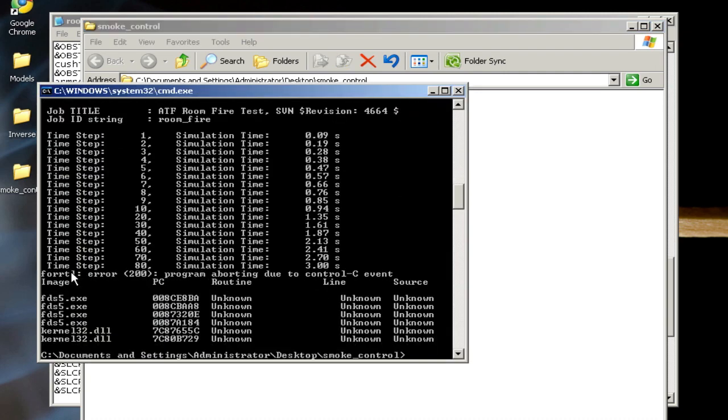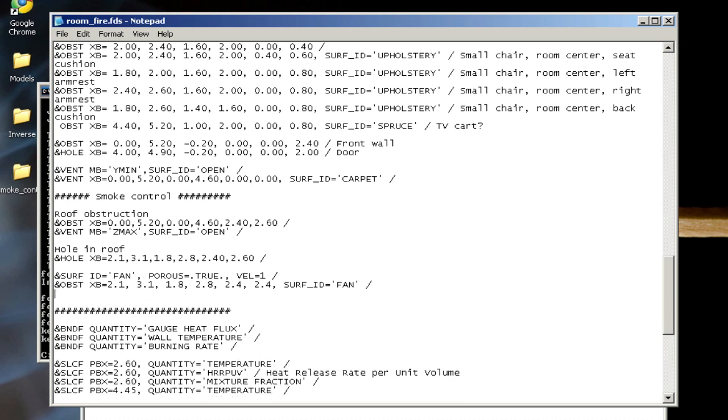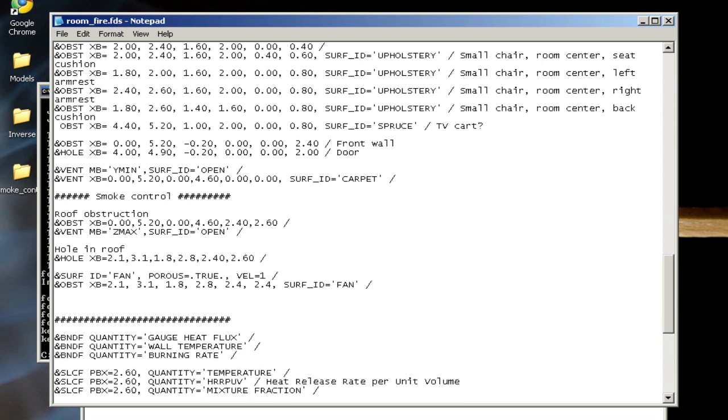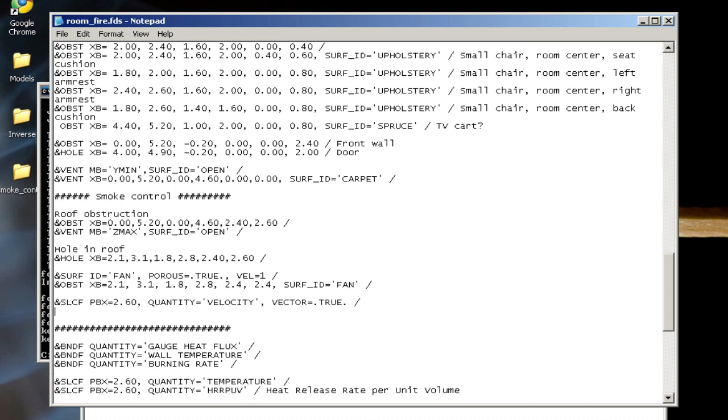Hit Ctrl+C to stop the simulation. Going back to my input file, I'm going to add a line for slice file PBX equal to 2.6, which is the middle of the room. I'm going to set the quantity to velocity and set vector equal to true. What that's going to do is give me little vectors in that slice region to show me the direction and magnitude of flow.